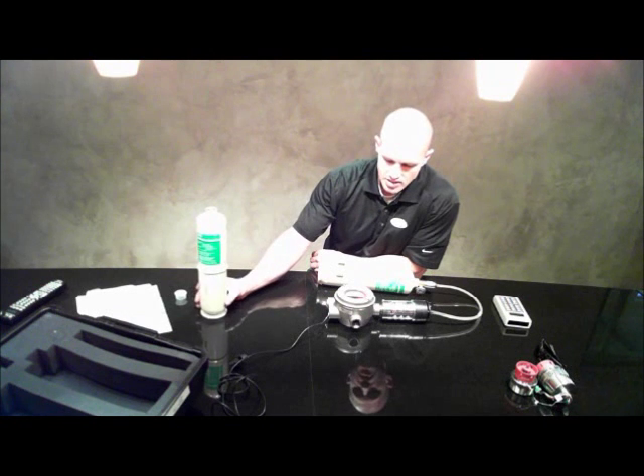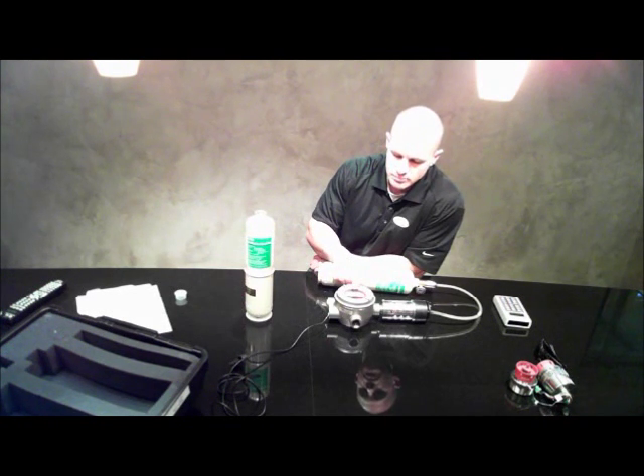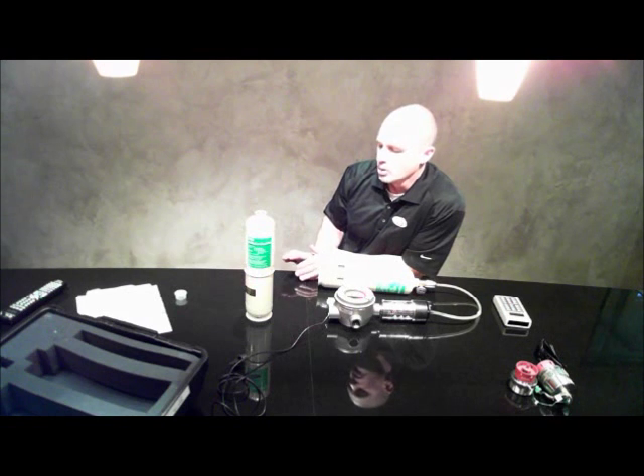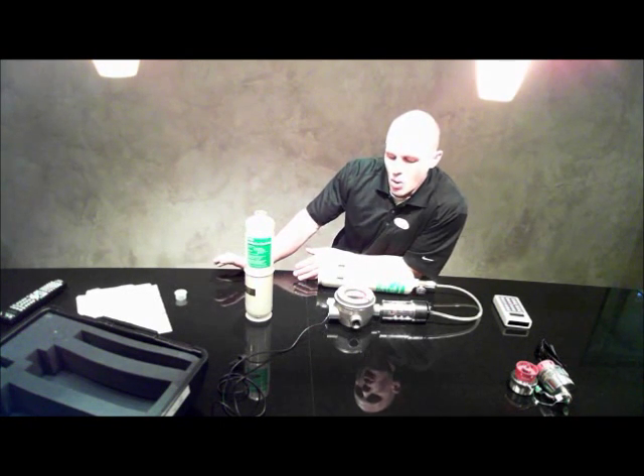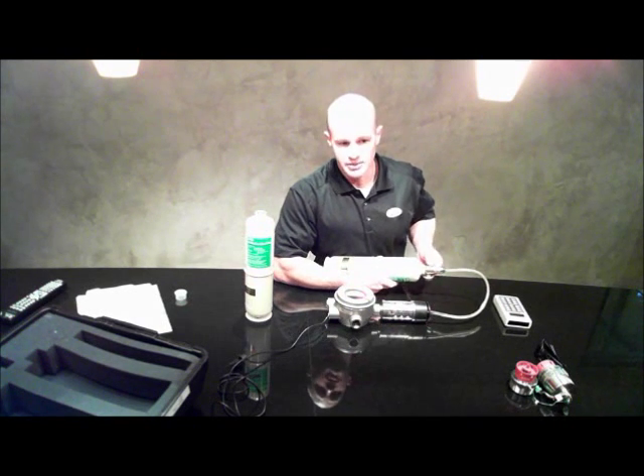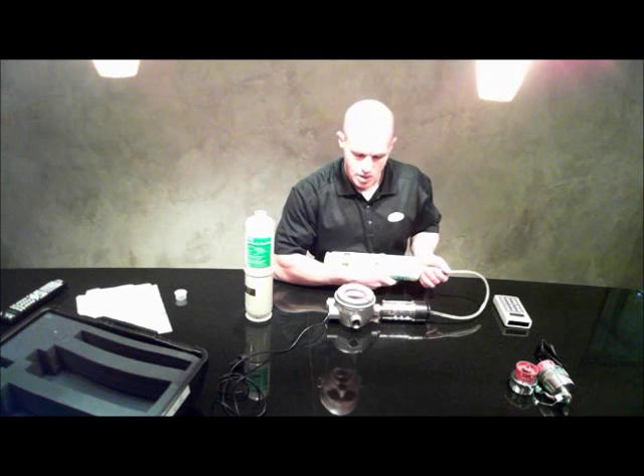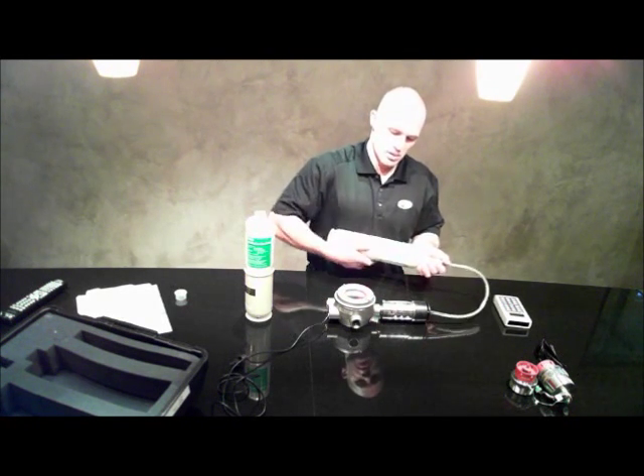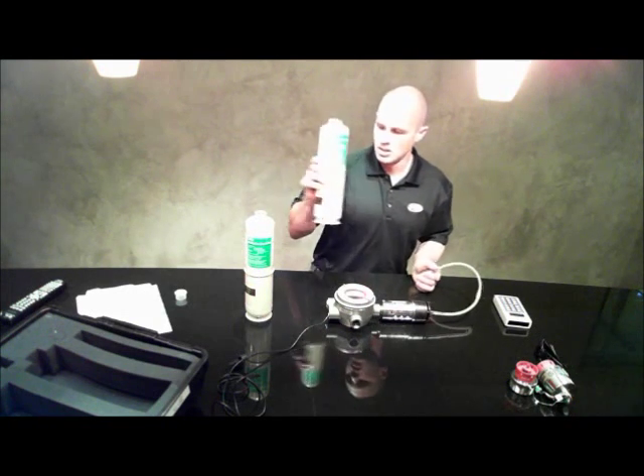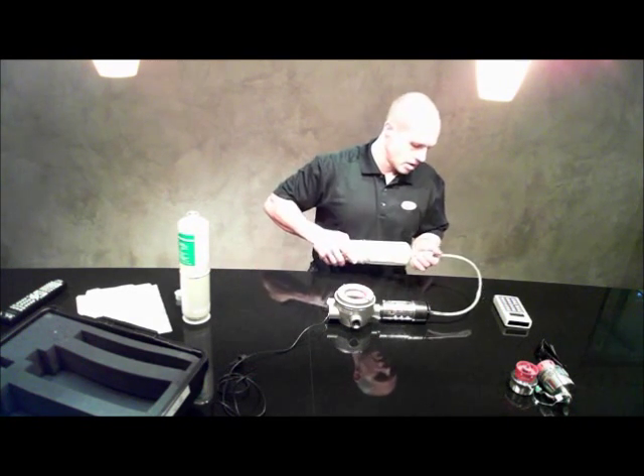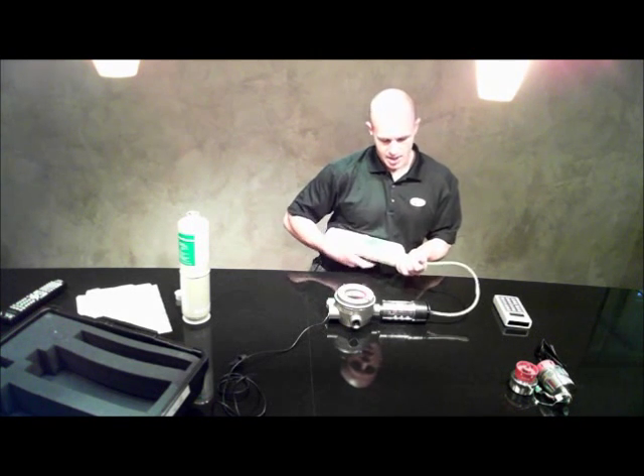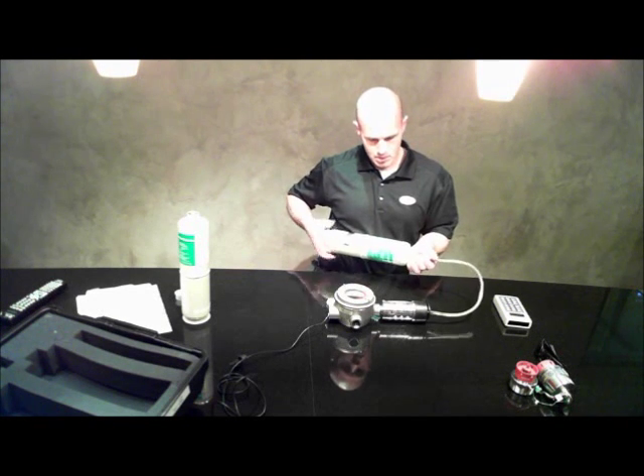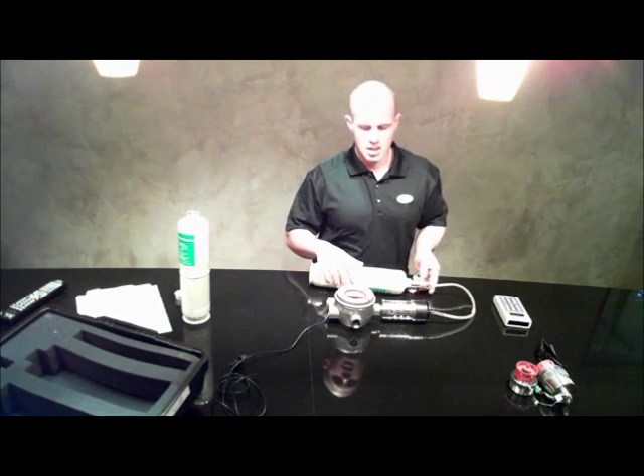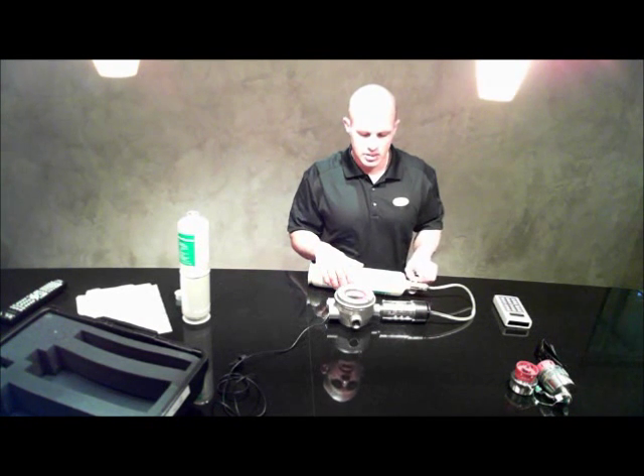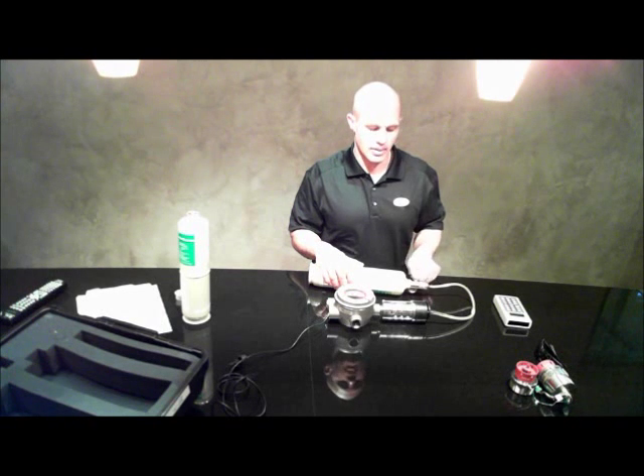So we'll run through this process. It shows that it's an initial calibration. It says iCal on there. An initial calibration is typically performed when you put a brand new sensor into service, or you've got a sensor that's in some kind of troubled fault that nothing else will clear out. So now it's saying apply span gas, and it gives me another 30 seconds to take the zero gas off and rig up the span gas. Got about 12 seconds. And again, the gas doesn't need to be flowing during the countdown. I usually let it start flowing in about 5 seconds or so if I'm right up next to the sensor.